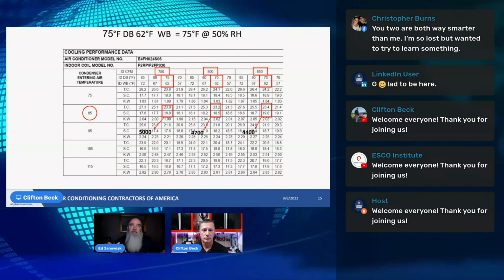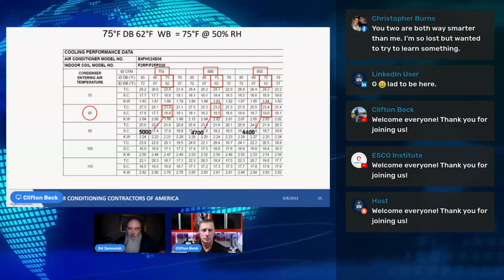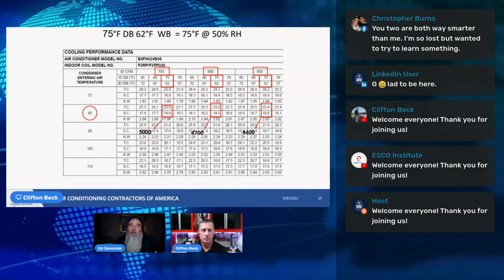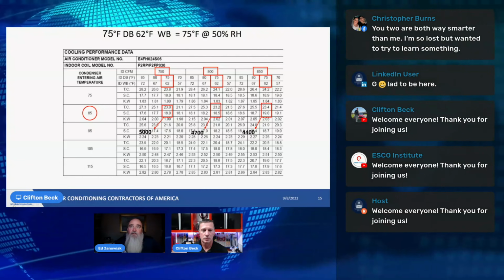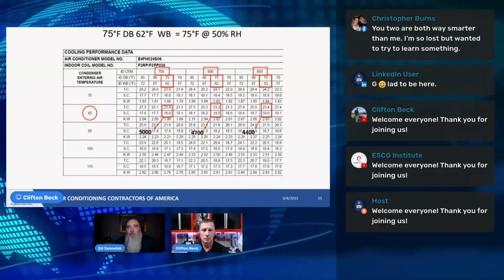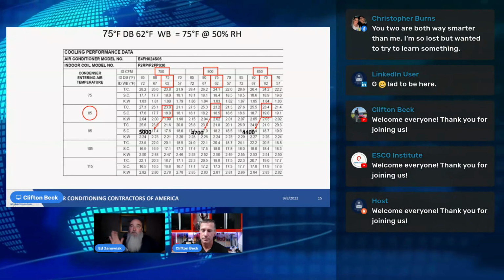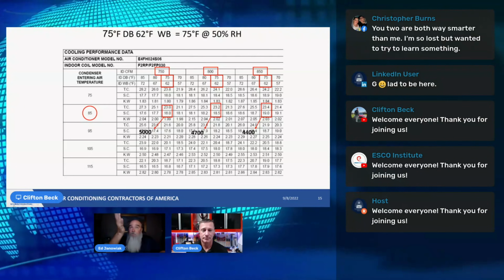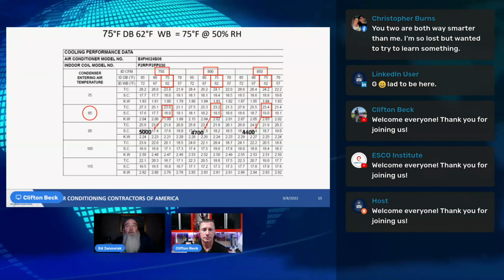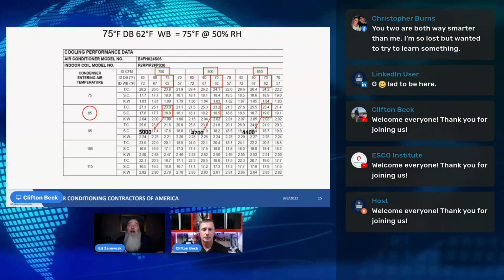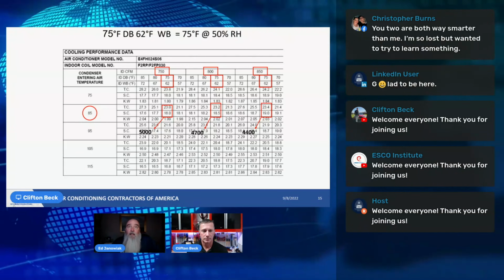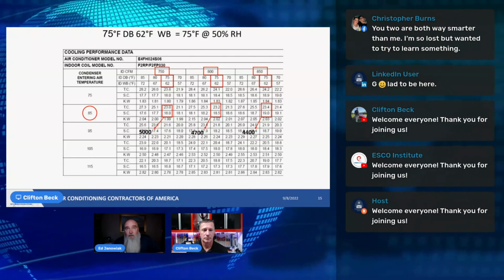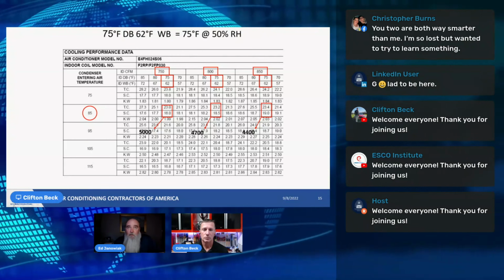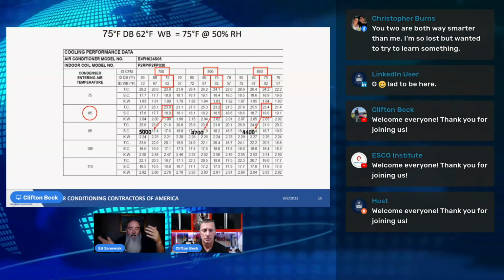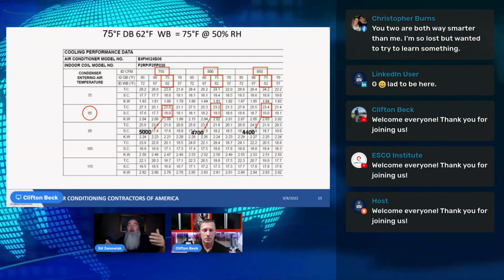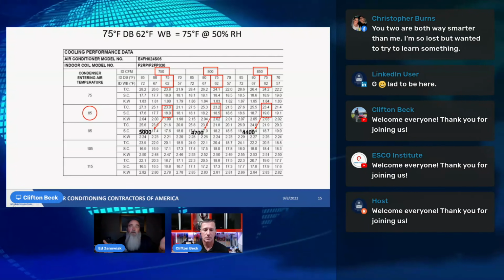Under the 850, it says 75/62 at 75 degrees at 50% relative humidity. If you follow that down to the next box, the top number is telling us our total capacity at 85 degrees outside. That's just a random outdoor temperature. 23,000 BTUs. Right. So it's 23,400 BTUs of total capacity. The box below it is sensible capacity. And if you deduct the 19K from the 23.4, we get 4,400 BTUs of latent capacity. That's the way you extract the three values that are required for proper equipment expanded performance data.